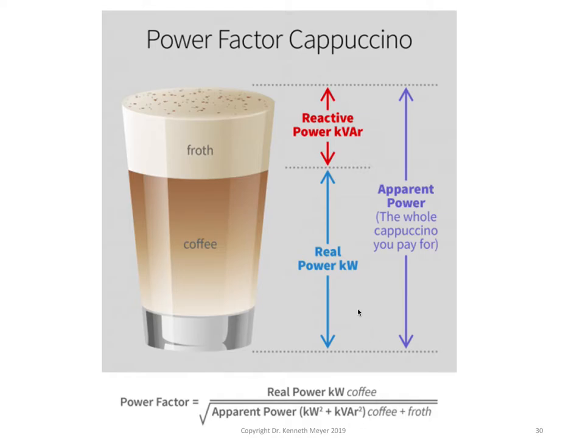I've been in factories where the bill for the month might have been about $25,000 for real power, but the kVAR charge was another $15,000 on top of that, because they hadn't done anything to correct their power factor. So supply authorities have two parts to their bill. They have the kilowatt hour charge and they have the kVAR demand charge, which can be very, very substantial.